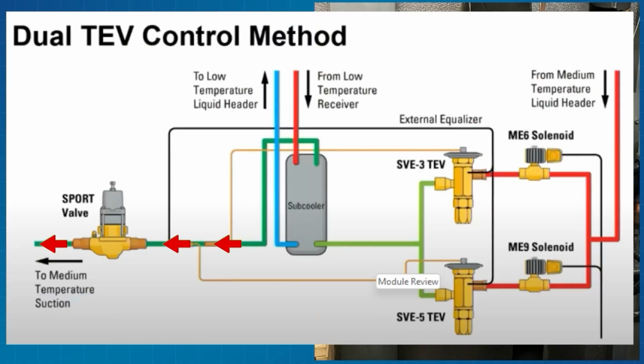So what does that mean? Well, that means I've got liquid refrigerant in here instead of vapor, and it's not superheated, right? So what does my TXV think is going on? Starving. It thinks it's starving. What's it going to do? More liquid, more. It's going to open. Why does it think it's starving? Because I don't have superheat. It's not a cold suction line. It's a warm suction line, and the warm is telling the TXV, oh, refrigerate more. Your superheat's going to be higher even though you're flooding.